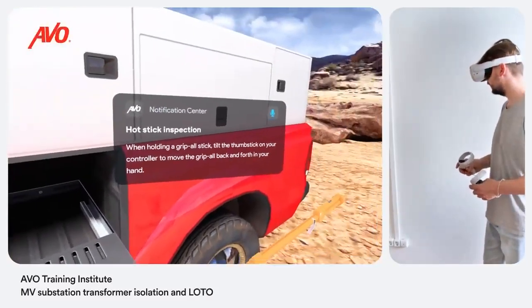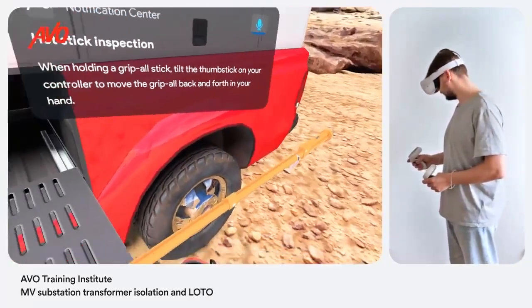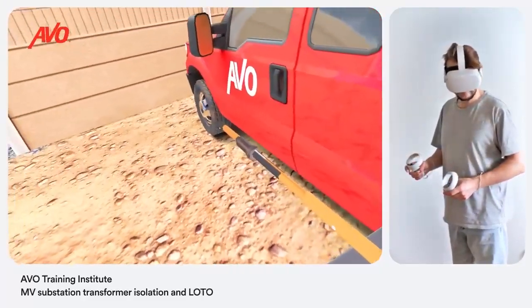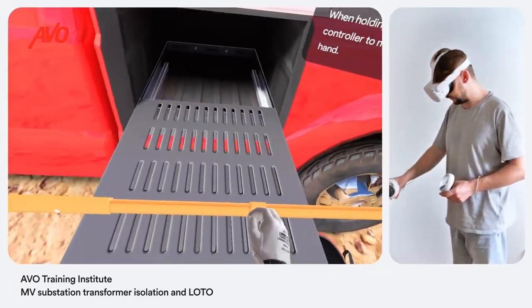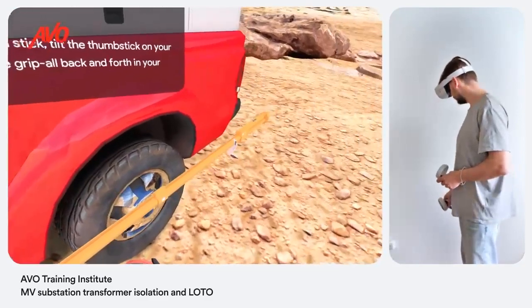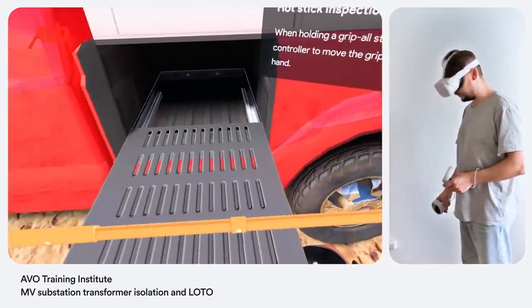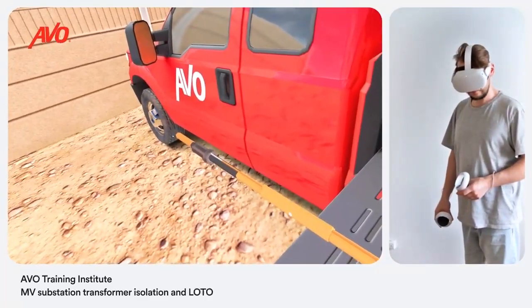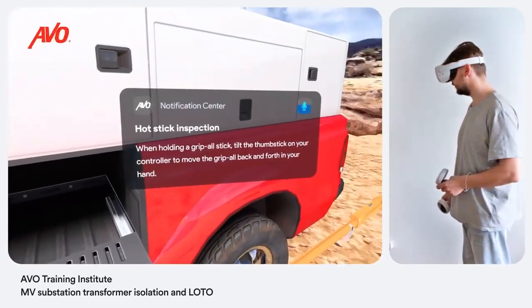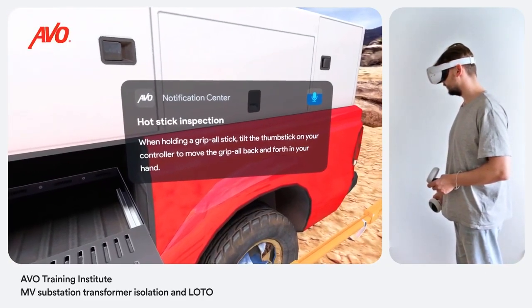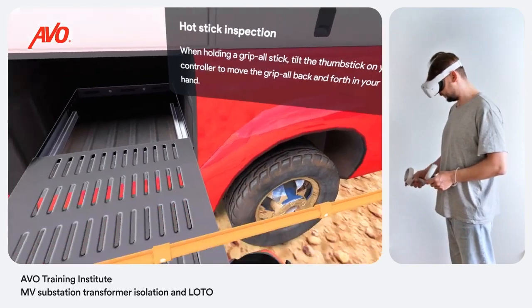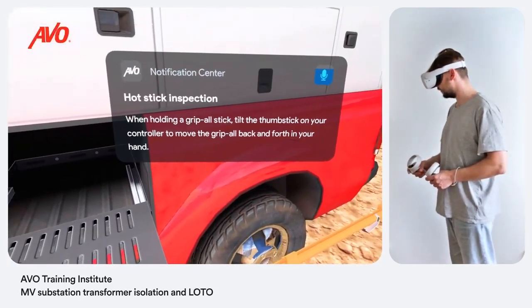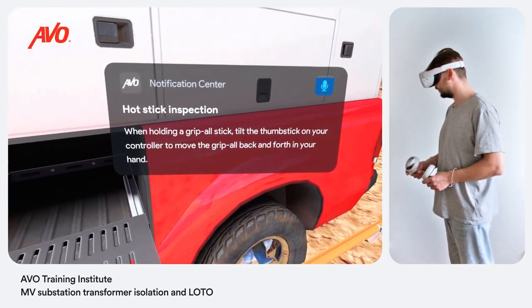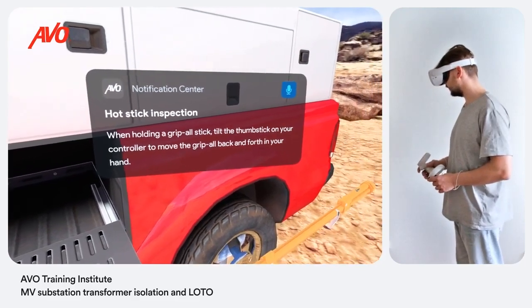A grip-all stick is required when working around energized power lines. You need to inspect the surface of the hot stick for scratches, gouges, cracks, cuts, nicks, and dents, dull finish, excessive wear and delamination, signs of electrical tracking, burn marks, or blistering. Also, inspect end fittings and other mechanical parts for proper operation, cracks, bending, or other visible damage or excessive wear.